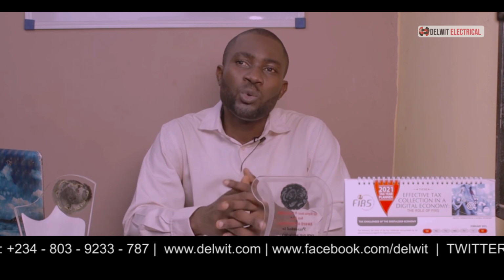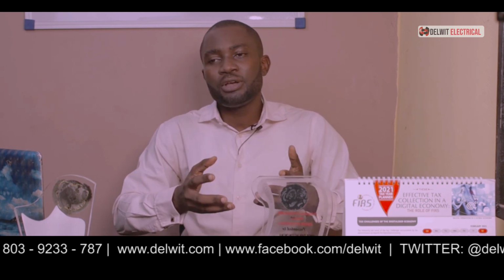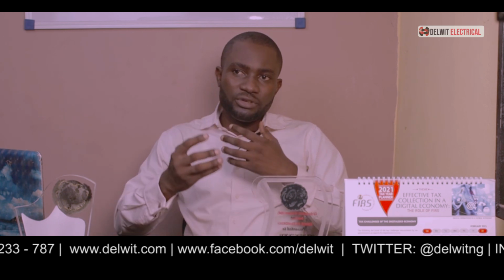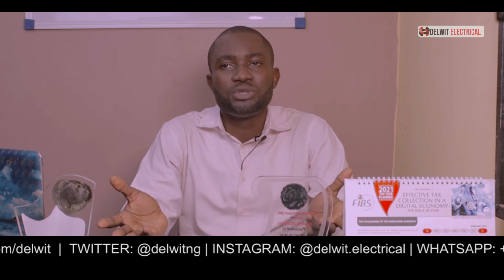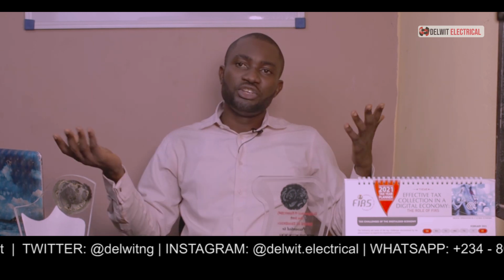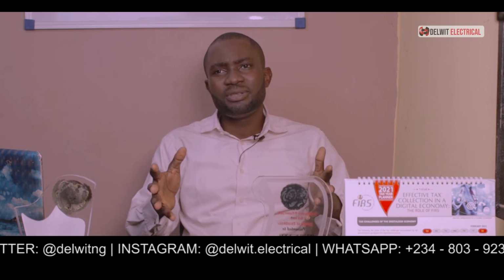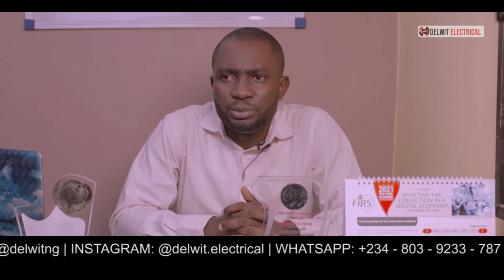And finally, older circuit breakers. Now, when a circuit breaker becomes old or you have used it over the years, it becomes too sensitive. So for every little thing, it trips. When you trace, you see that there is no fault. Just that the circuit breaker is just too sensitive. So in that case, you change your circuit breaker. So these are the little things that cause the tripping of a circuit breaker.